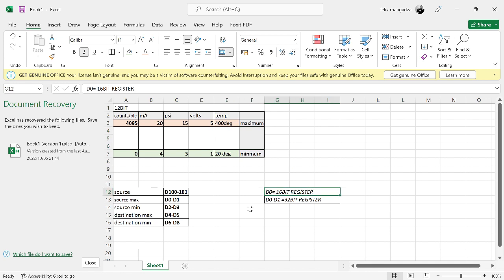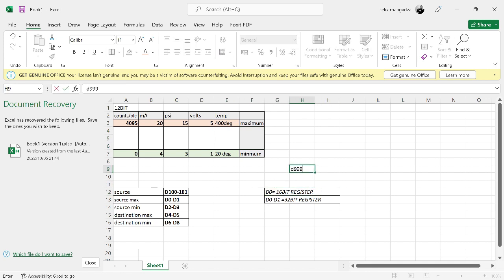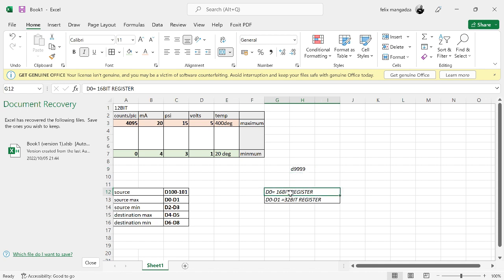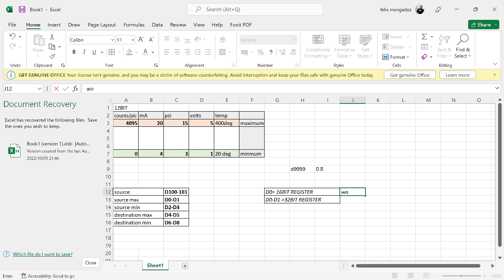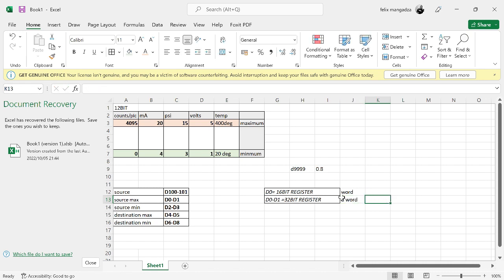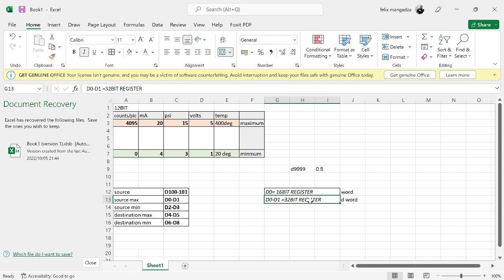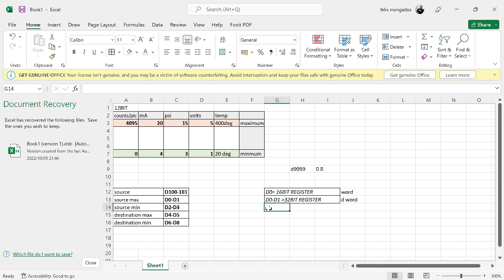The PLC has got registers from D0 to D9999. Each consecutive register has a memory of 16 bits — it's a 16-bit register in memory size. So if you want to store a floating point, a zero-comma value, you need a double word. A floating point occupies two consecutive devices, so you need D0 plus D1 to store a value like 0.8 in a double-word memory in the PLC. Whenever you move this value into D0, it will automatically occupy D0 and D1.